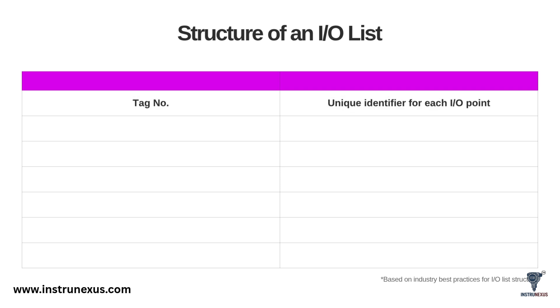Let's look at the anatomy of a typical IO List. While formats can vary, they all contain the same core information, as shown in this table, which is based on industry best practices. Every single IO point gets a row, and each column details a specific parameter. Tag No. is the unique identifier for the IO point, like LT-1001.